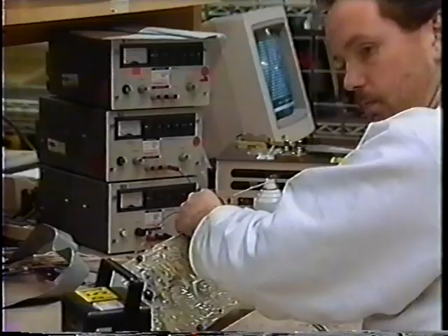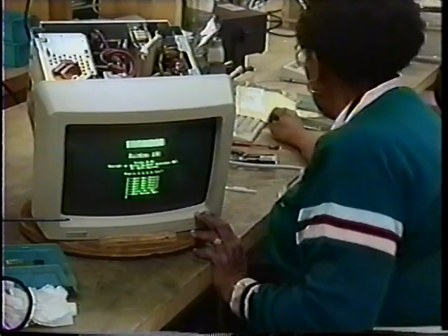High-voltage workstations present unique issues in the control of electrostatic discharge. Generally, safety experts consider a workstation to have hazardous potential if it has open, exposed metal parts, with the possibility of accidental contact at over 42.4 volts peak AC or 60 volts DC, and capable of supplying a current greater than 0.7 milliamps peak or 2 milliamps DC. Examples of high-voltage workstations include high pot testing, power conditioner testing, video monitor testing and alignment, and uninterruptible power supply testing.